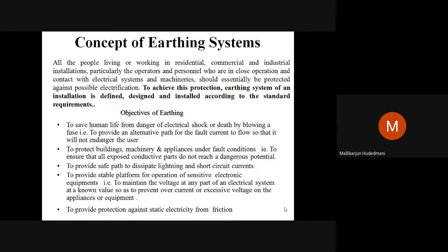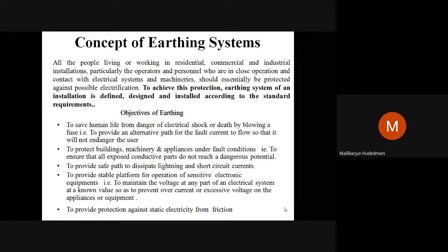To protect buildings, machinery and appliances under fault condition, that is, to ensure that all exposed conductive parts do not reach a dangerous potential. This is what I was speaking. Metal enclosures of the electrical gadgets are connected to the earth point. It means that if any high voltage is induced in them, it will be driven to the earth potential. Therefore, it safeguards the operator who comes in contact with it.